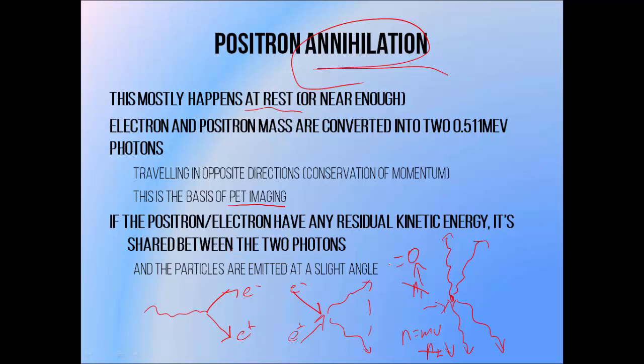The basic process involves using the detection of annihilation photons in order to locate radioactive material within a patient. A PET scanner is basically a ring of radiation detectors. When a positron annihilation occurs inside the ring, it will emit photons in exactly opposite directions. When two photons are simultaneously detected by the ring, we are able to determine that a positron annihilation has taken place somewhere along the line connecting the two, allowing us to determine the approximate location of positron-emitting radioisotopes within the body.